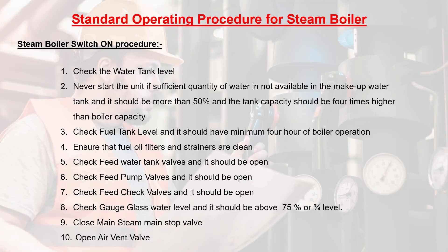Step 7: check feed check valves — they should be open. Step 8: check the gauge glass water level — it should be at 75% or three-quarters level. Step 9: close the main steam stop valve.